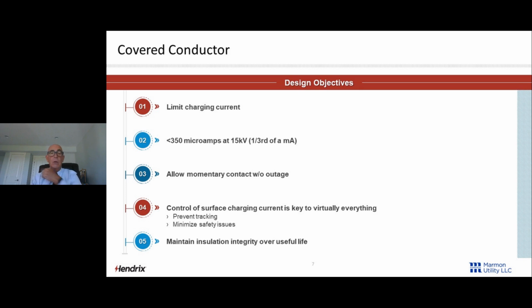And we say that controlling the surface charging current is key to virtually everything. We want to prevent tracking. We want to minimize safety issues in case anybody does touch it. We don't want to have an issue. And we want to make sure that with that current floating around the outside of that jacket for 40, 50, 60, 70 years, it's not going to degrade the quality of that insulation. We're not going to have PD. So we want to maintain that insulation integrity over the entire useful life of that system.